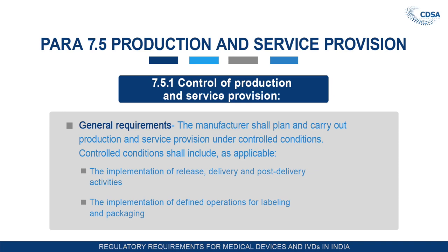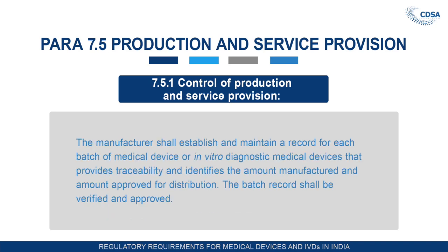The implementation of defined operations for labeling and packaging. The manufacturer will establish and maintain a record of each batch of medical device or in vitro diagnostic medical device that provides traceability and identifies the amount manufactured and amount approved for distribution. The batch record shall be verified and approved.